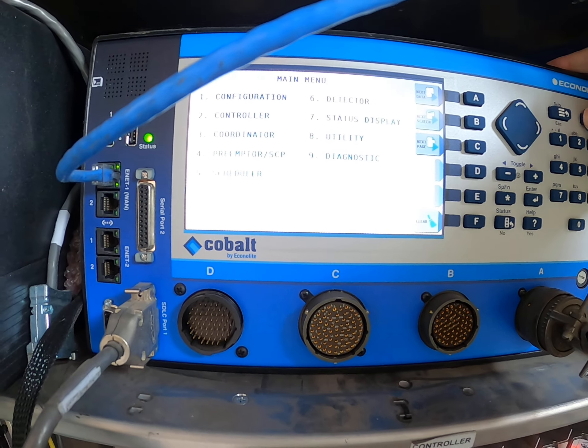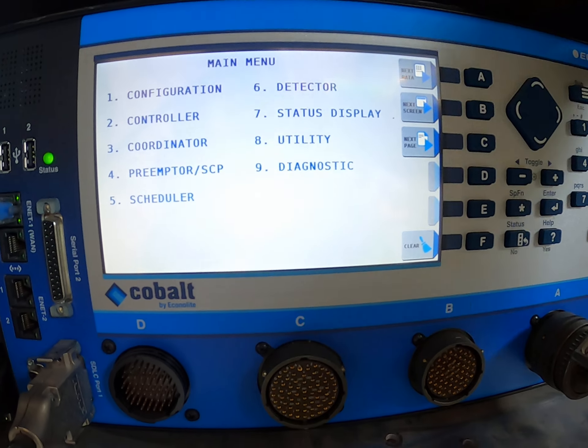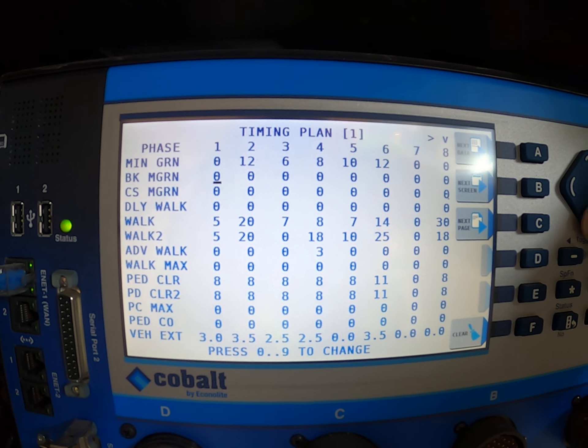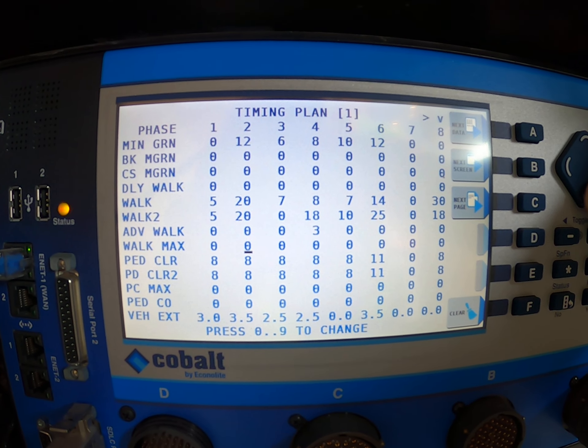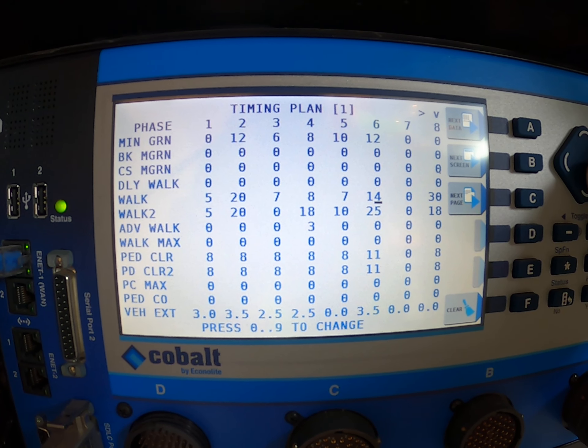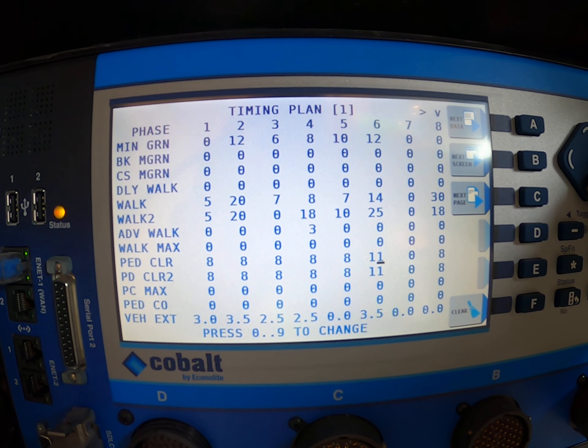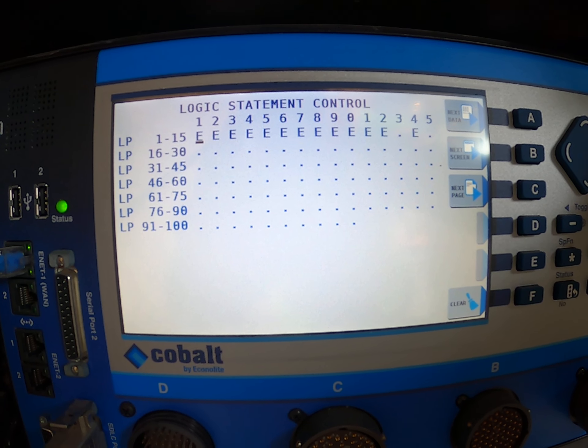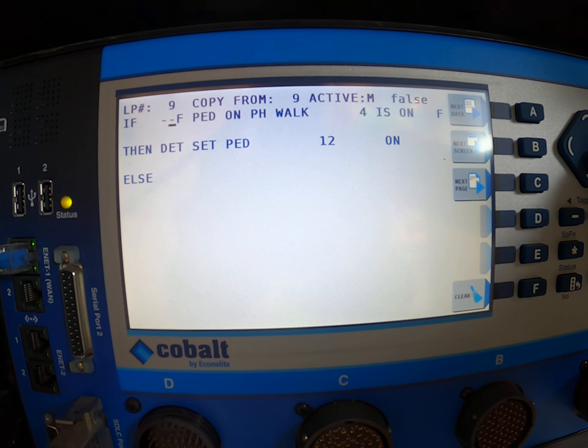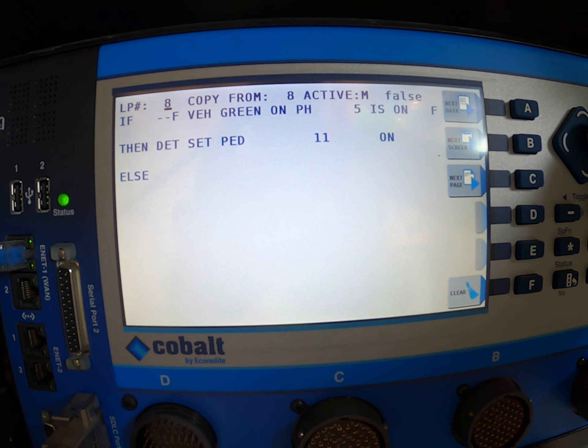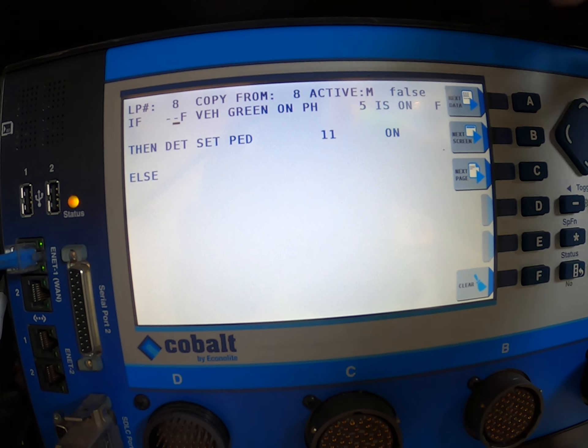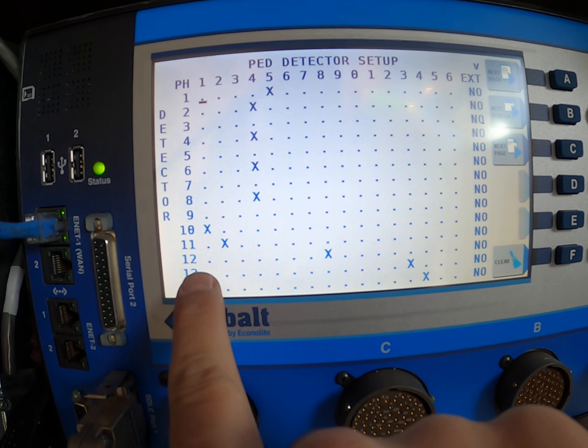So if we come to the controller here, that logic statement — first we go to the timing plan. Our phase two walk is 20 seconds, flashing don't walk is 8 seconds. Our phase six uses the 14-second with 11. We go to our logic processor and go to the correct logic step, which says: when vehicle green on phase five is on, then set ped detector 11 on. Ped detector 11 calls ped phase two.